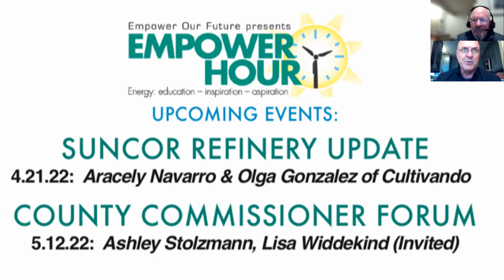It's something utilities do all the time, even with the regular system, called cold load pickup. They'll go out and sectionalize the lines, disconnect portions of the line on the way back to the substation, start at the substation, and pick up the closest loads first because they'll all come on at once and be a big load. Then they go down the line, closing in additional disconnect points and slowly bringing the system back up. That's what we did back in the days of big winter storms, called cold load pickup. It's very similar to black starting.